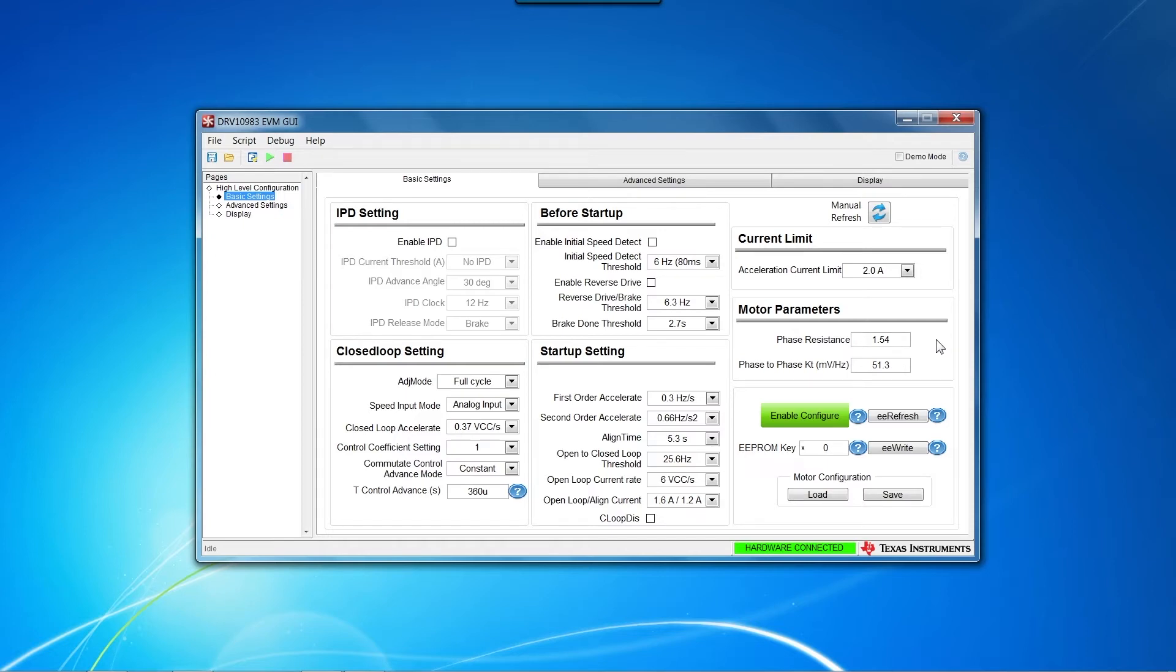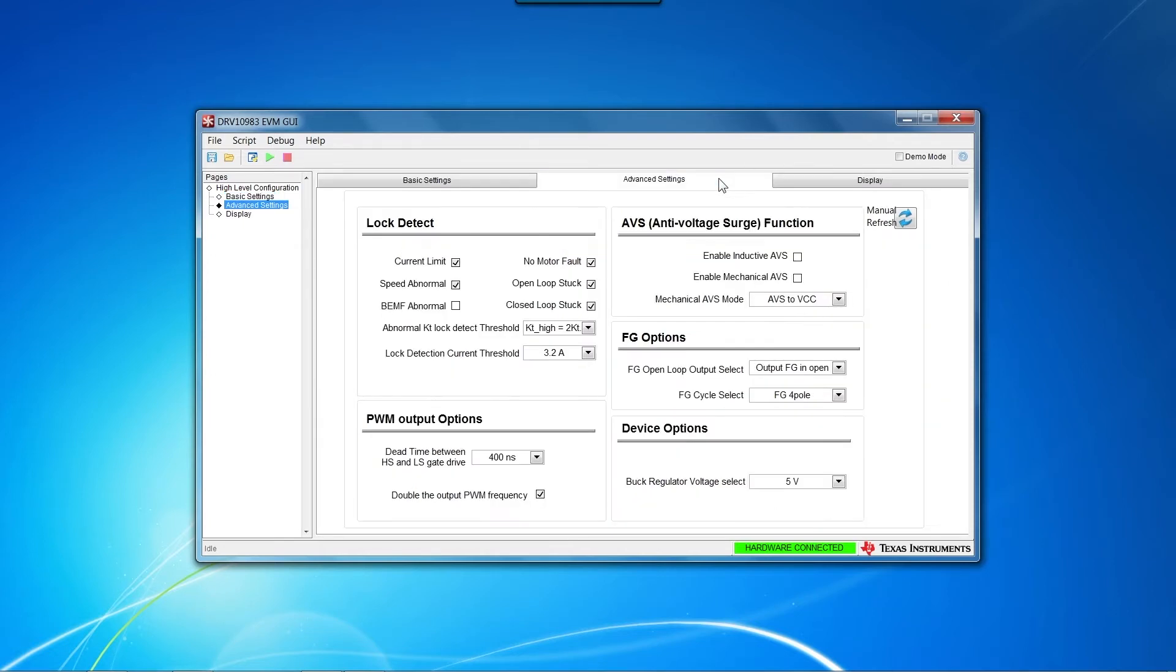Now, go to the Advanced Settings tab and ensure the settings in the Lock Detect, Anti-Voltage Surge function, Pulse Width Modulation output options, FG options, and Device Options sections match the settings shown here.